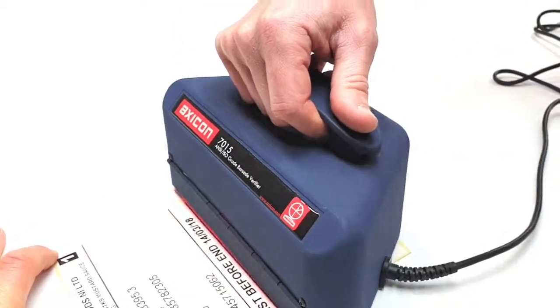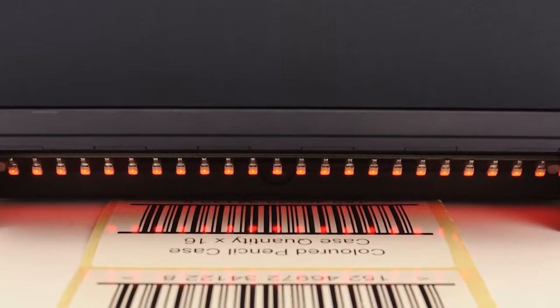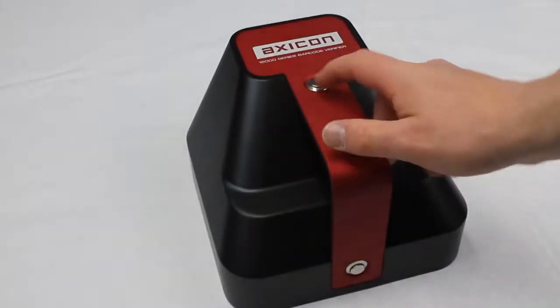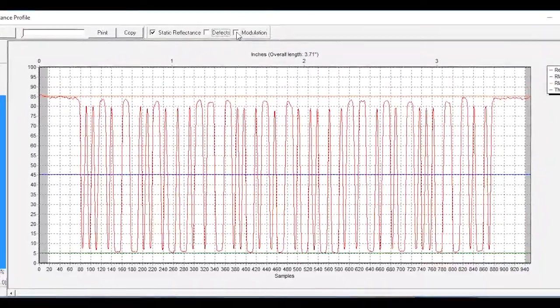All AXICON verifiers are designed to be used for hundreds of hours without any maintenance, but over time the red LEDs will begin to fade. This is true for all LEDs. Dust may also begin to appear in the verifier as well. AXICON's barcode verifiers are high-precision optical devices designed to be used in working environments. We therefore recommend that they are serviced every year to ensure that they still conform to the relevant ISO IEC standards.